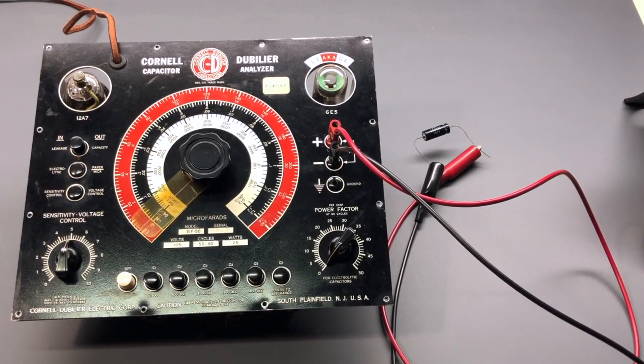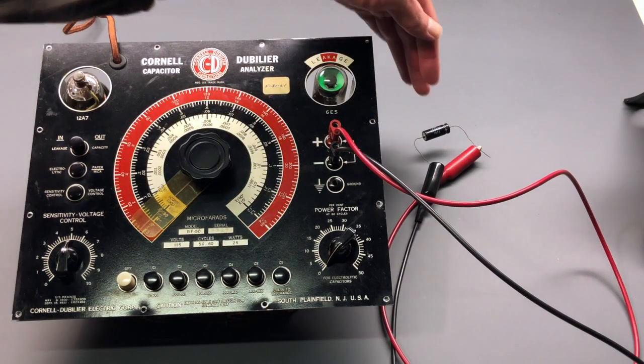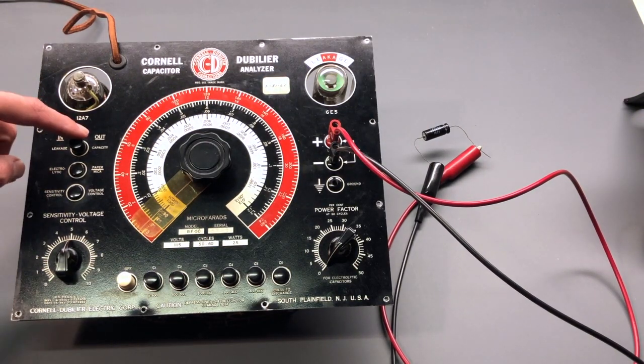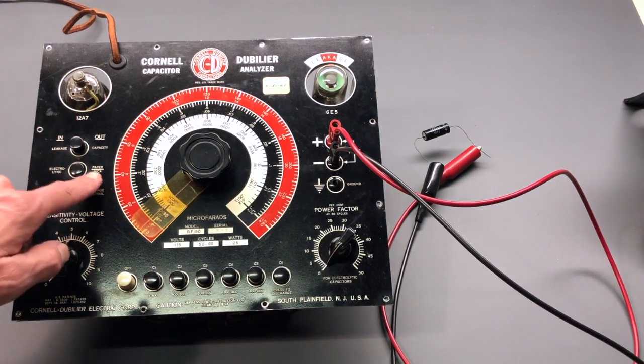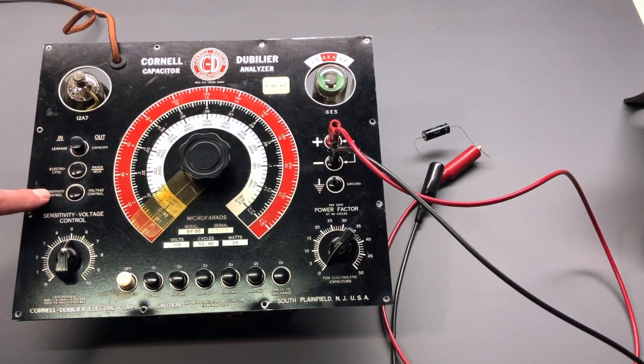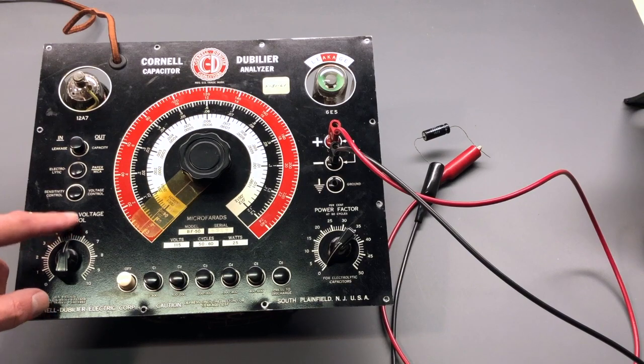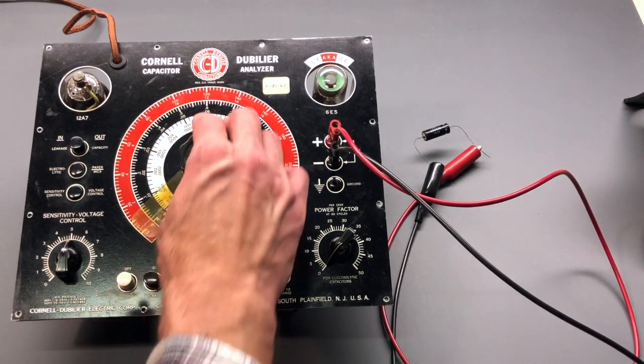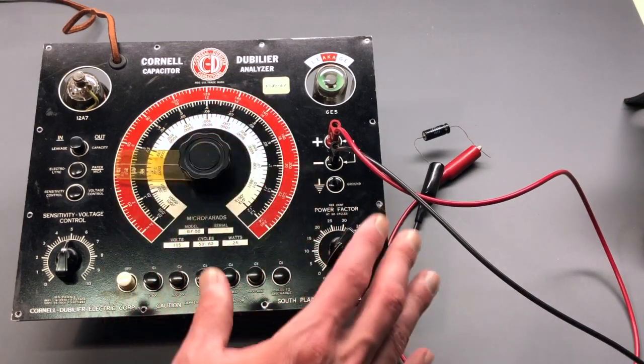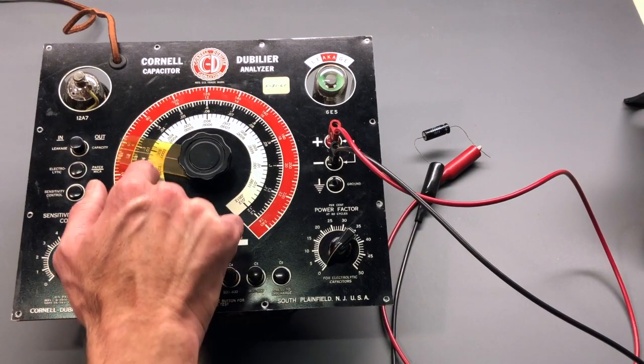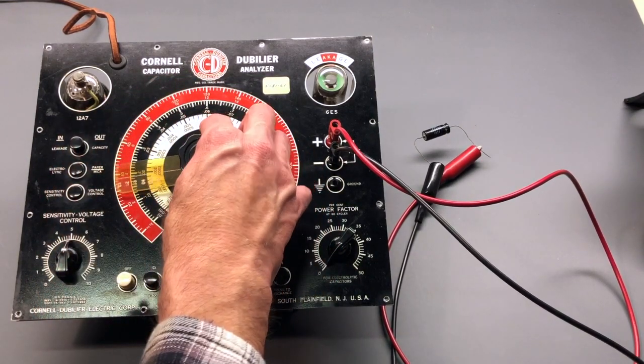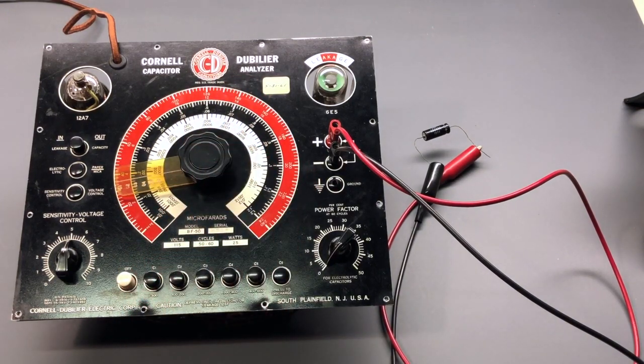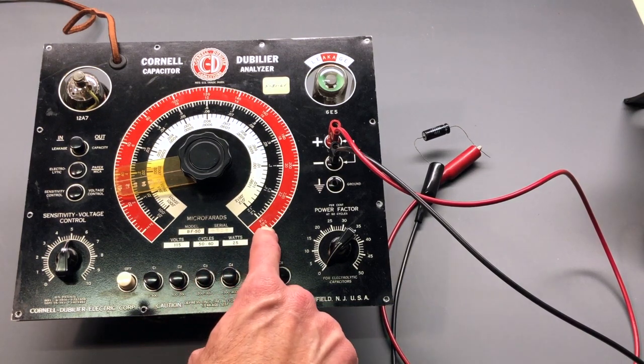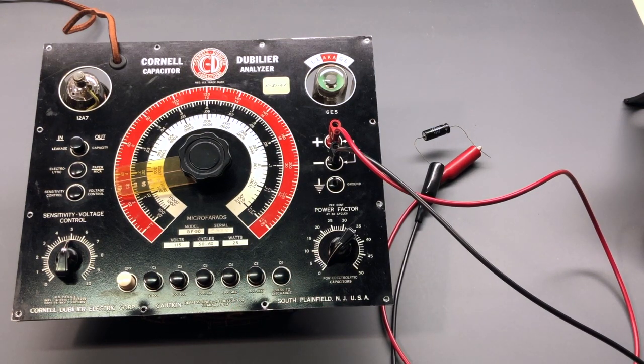Okay, I have the tester configured for the capacity test. We're using that same 3 microfarad capacitor, and the switches have been set for capacity, so the top switch is out or up. This is set for electrolytic, which is in, and this is in, which is sensitivity control, which I have at about mid-scale. Now, for this test, this is rotated, and the actual value of the capacitor is read, where this line, of course, corresponds to the different values of capacitance. The range on this meter is from 0.00001 microfarad, which is also equal to 10 picofarad or 0.01 nanofarads, and then a maximum of 240 microfarads.